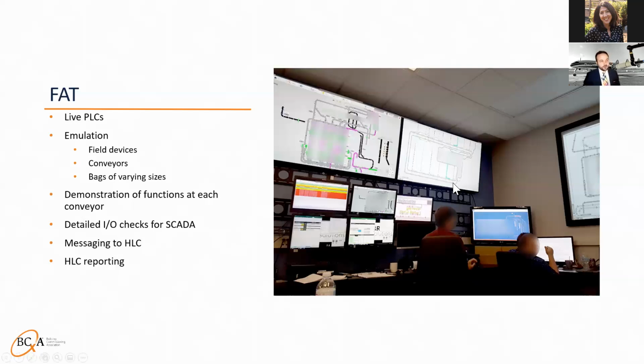In the FAT, you can do very detailed I/O checks, so you can make sure that the PLCs or the port numbers used on the PLCs match what the intended function is. In the past, a lot of this I/O check was done in the field, but when you have many thousands of points, that can become very tiring, and also just because of the rote nature of it, the accuracy of that kind of commissioning goes down. Doing it in an office like this allows people to focus, take breaks for a bit, come back, and go through and ensure a high level of quality on those checks.